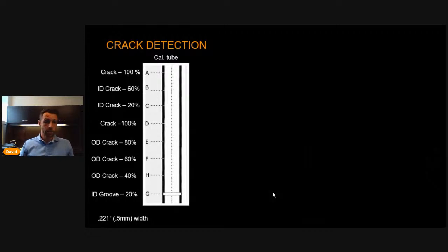On the crack detection, here we had a tube that we scanned in our lab. It's a calibration tube. We see we have a few cracks in there. The first top three are ID cracks, one is through wall 100%. And then at the bottom, we got OD cracks. And at the very end, the ID groove 20%.